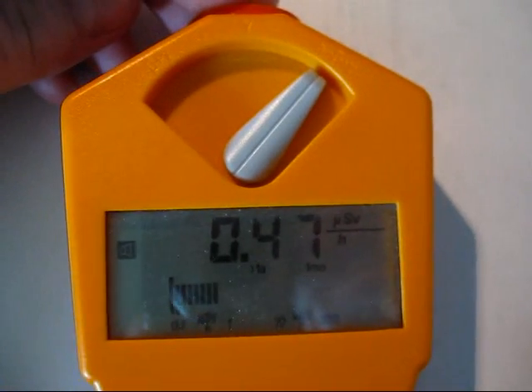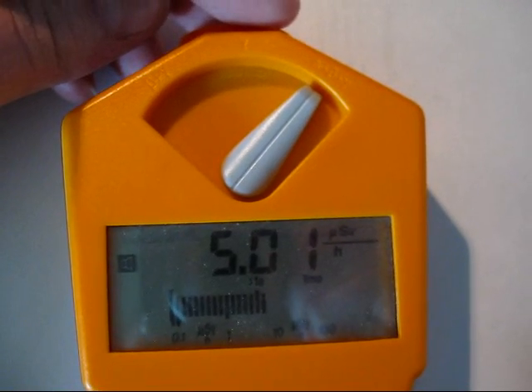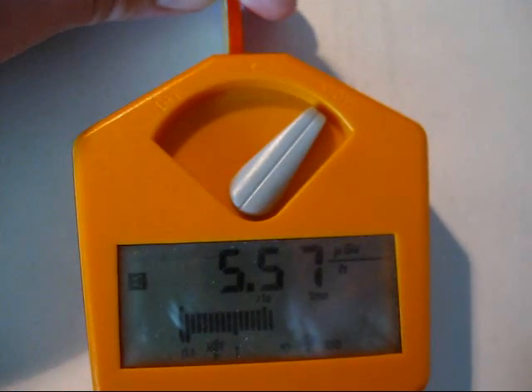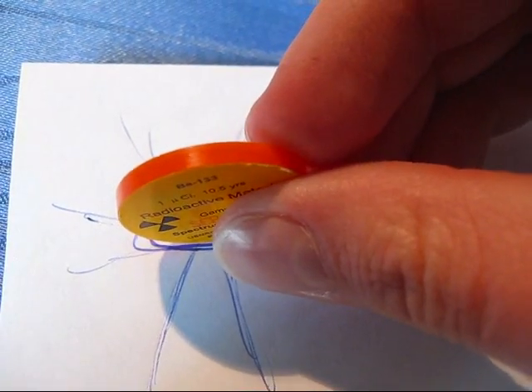We'll just verify this with our device. Let's hold one source in front with the proper side. Let's flip the source around. Okay, still a reading, and from the sides, yep, still a reading as well. So that is our radioactive source.